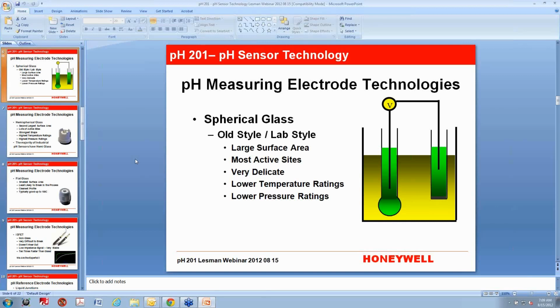However, it's very delicate due to its physical construction. It's very easy to break the glass either by mishandling, say in a beaker when you're doing a buffer calibration, or just in the process. These tend to have lower temperature ratings and lower pressure ratings to keep the impedance down. So they're not quite as tough against high temperatures, high pressures, and they're not really happy in really extreme pH applications as well.